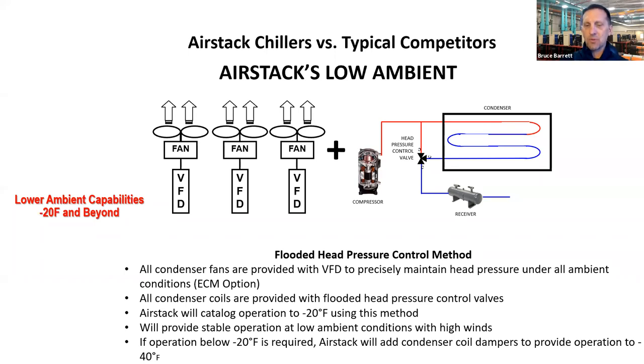We can go down to minus 20 as standard with that flooded head pressure control methodology. We've even done jobs down to minus 40. We've got some air-cooled chillers in Antarctica right now. Of course, they've got free cooling. Hopefully that free cooling is enough capacity to carry them at some point. But if a free cool gets a leak or something happens to the fans, they do rely on their mechanical cooling all the way down to minus 40. That's a big difference between packaged chillers and modular chillers, being able to do flooded head pressure control in that environment.